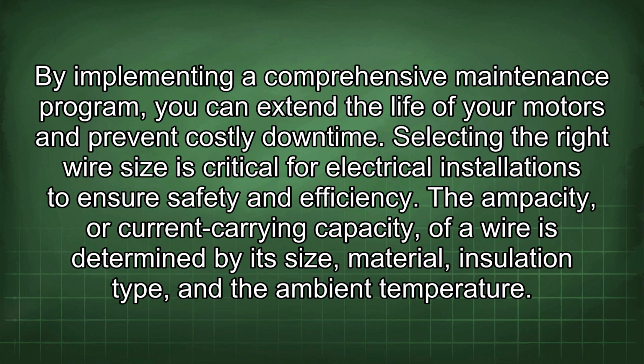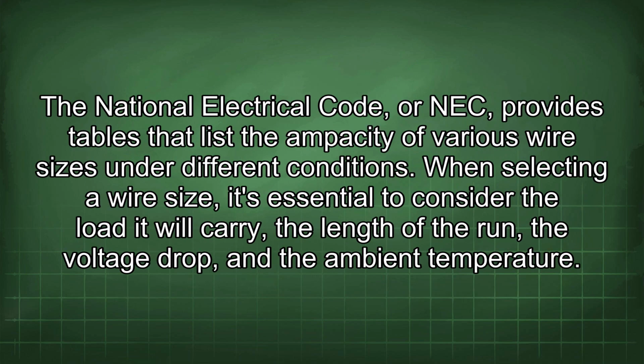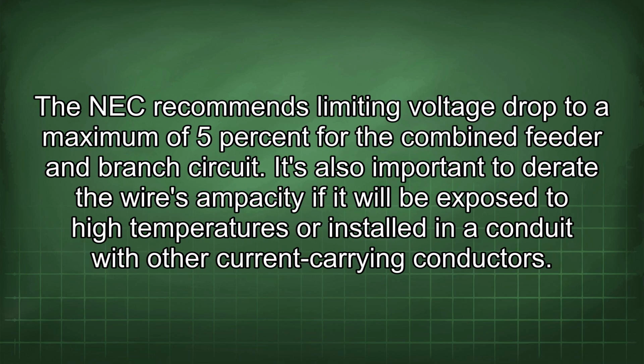The ampacity, or current carrying capacity, of a wire is determined by its size, material, insulation type, and the ambient temperature. The National Electrical Code, or NEC, provides tables that list the ampacity of various wire sizes under different conditions. When selecting a wire size, it's essential to consider the load it will carry, the length of the run, the voltage drop, and the ambient temperature. The NEC recommends limiting voltage drop to a maximum of 5% for the combined feeder and branch circuit.